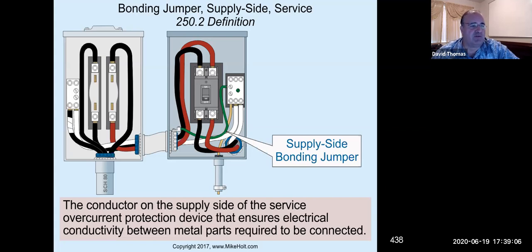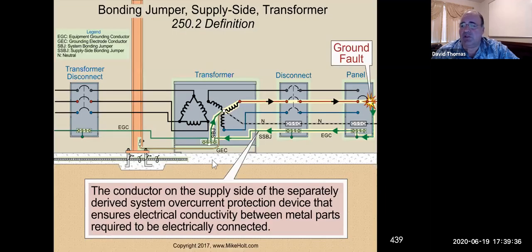You have to know how this system works: all electrons that get induced into our equipment ground want to go back to the source, which is the transformer, or any separately derived source. A transformer is separately derived, right? So let's look at this next picture, because it talks about the bonding jumper on the supply side.